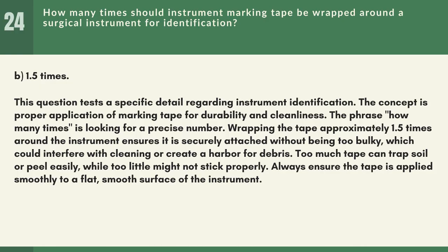The concept is proper application of marking tape for durability and cleanliness. The phrase "how many times" is looking for a precise number. Wrapping the tape approximately 1.5 times around the instrument ensures it is securely attached without being too bulky, which could interfere with cleaning or create a harbor for debris. Too much tape can trap soil or peel easily, while too little might not stick properly. Always ensure the tape is applied smoothly to a flat, smooth surface of the instrument.